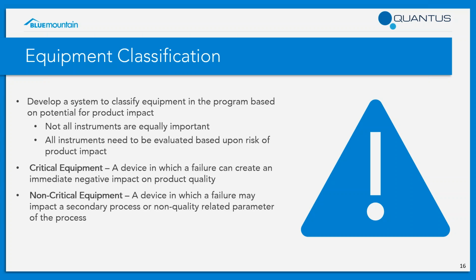From a real high level overview, we're trying to put instruments into two categories. It's going to be your critical equipment that's going to have a direct impact on product, patient, or safety. So you want to think about a sterilization temperature probe on an autoclave. If we were to find that out of tolerance during a calibration, we could have a direct quality event related to the sterilization of materials or products. And then non-critical equipment may have a secondary impact to your process or a non-quality related parameter. So if we stick with that same autoclave example, we could think of a pressure gauge on the jacket of the autoclave. If this unit happened to be out of tolerance, it most likely would not impact the sterilization process, but it could be an indicator of other attributes of the system that may have been affected.